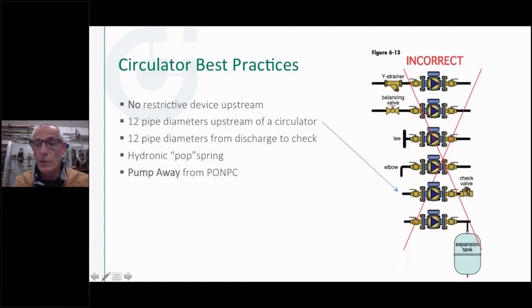And the other thing I wanted to show down here, on the check valve, I'd like to see the same thing, about 12 pipe diameters away. Now, I understand that a lot of circulators have check valves built right into them now, so it's not an ideal place to put a check valve, but again, maybe it's the lesser of two evils. If people weren't using check valves at all, it certainly is nice to have a check valve built right into the circulator, but ideally it would be a little distance away from it.